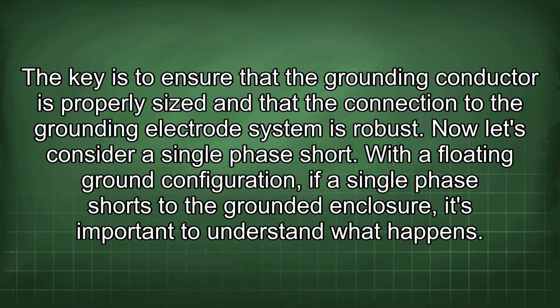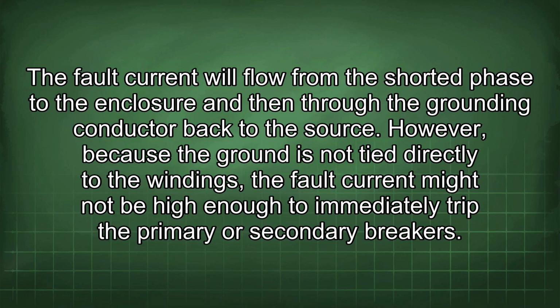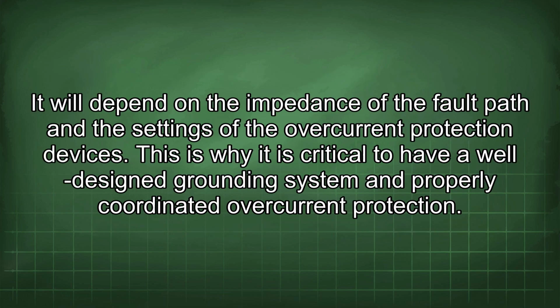Now let's consider a single phase short. With a floating ground configuration, if a single phase shorts to the grounded enclosure, it's important to understand what happens. The fault current will flow from the shorted phase to the enclosure and then through the grounding conductor back to the source. However, because the ground is not tied directly to the windings, the fault current might not be high enough to immediately trip the primary or secondary breakers. It will depend on the impedance of the fault path and the settings of the overcurrent protection devices.